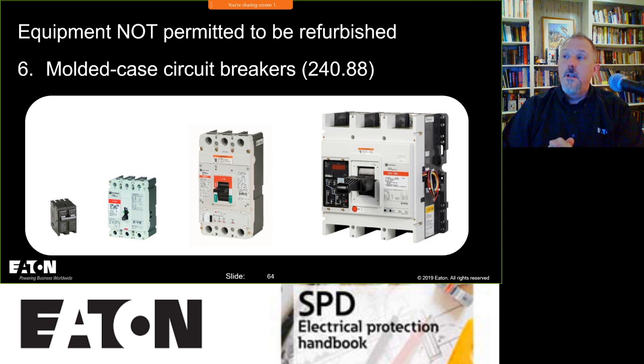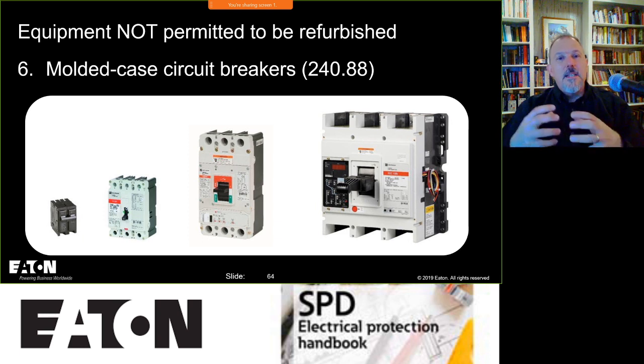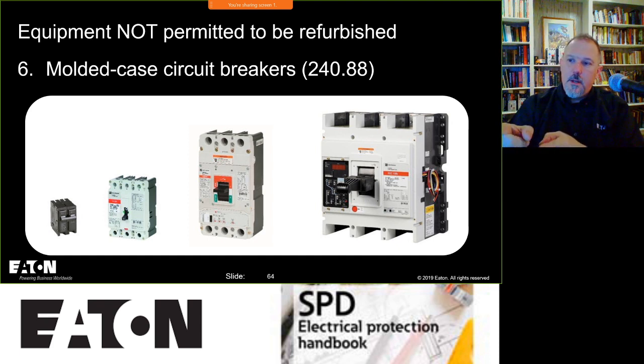So, molded case circuit breakers in 240.88. Now the trick here—the important thing to remember—is that insulated case circuit breakers are listed to UL 489, and that is a molded case product. So I'm showing our little BR breakers, the residential ones, all the way up through the big RD breaker, which I think is our biggest molded case circuit breaker. But you have to remember that an insulated case circuit breaker is also a molded case circuit breaker, because it's listed to UL 489.